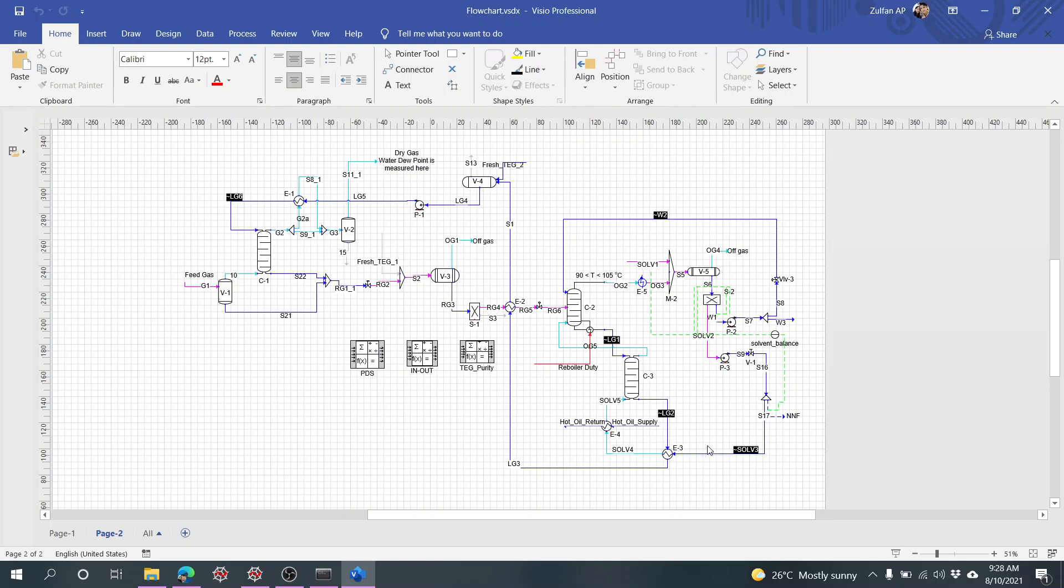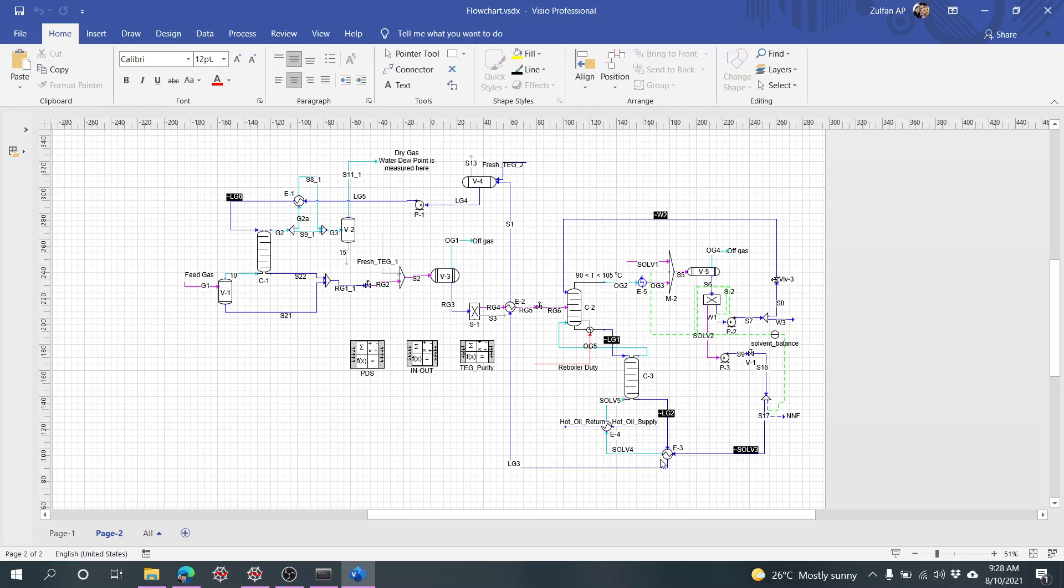In this case we have the feed gas which we use as an input, and then we have some operational variables that we apply in the plant. For example, the recycle water reflux flow rate, the flow rate of the solvent that strips out the remaining water from the lean glycol, the reboiler temperature which corresponds to the reboiler duty, and the lean glycol flow rate to absorb the water.